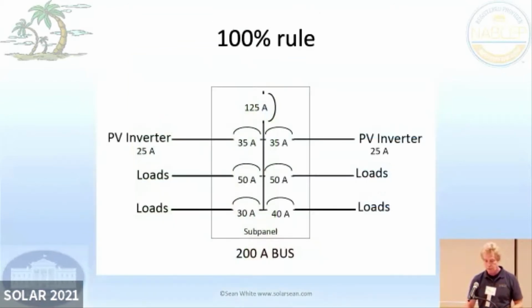And so the 100% rule, you don't have to put it at the opposite side, but you're more restricted. If we had a 200 amp bus bar here, you say that panel board's rated for 200 amps, and we put on a 125 amp main breaker, then I've got 75 amps to work with that I could put anywhere I want. So you could see that these have PV inverters right next to the main breaker. I like to call that the 100% rule. A lot of people call that the 100% rule, the way to do that.